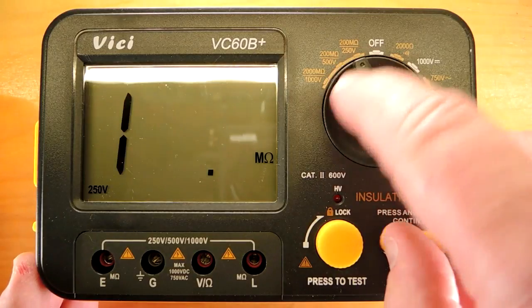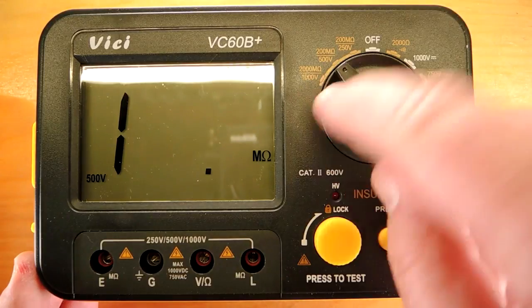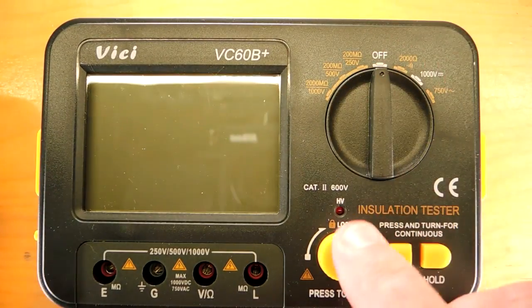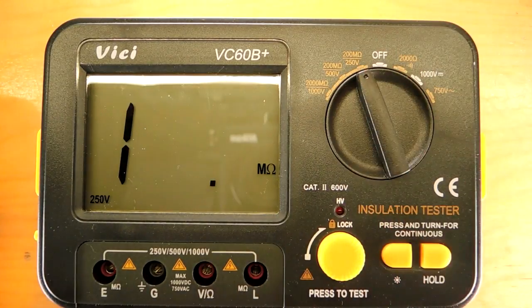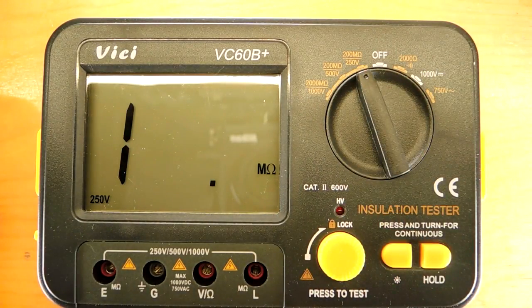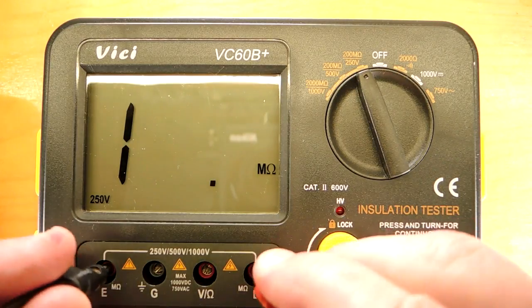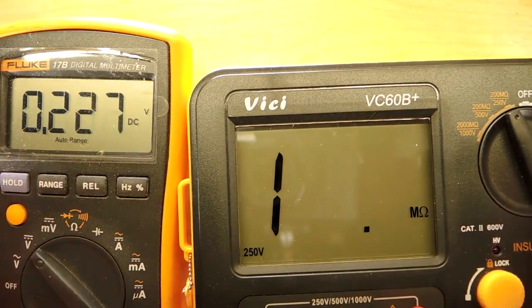There's a 250 volt, 200 mega-ohm range, a 500 volt, 200 mega-ohm range, and a 2,000 mega-ohm, 1,000 volt range. What this is doing is it'll actually generate a voltage at, say, 250 volts, and then it'll measure the resistance of the circuit. I'll get into why that's important. But for now, let's just connect it up to this Fluke meter and put it into voltage mode.